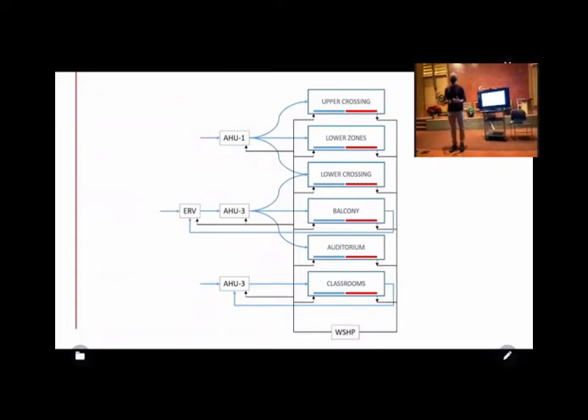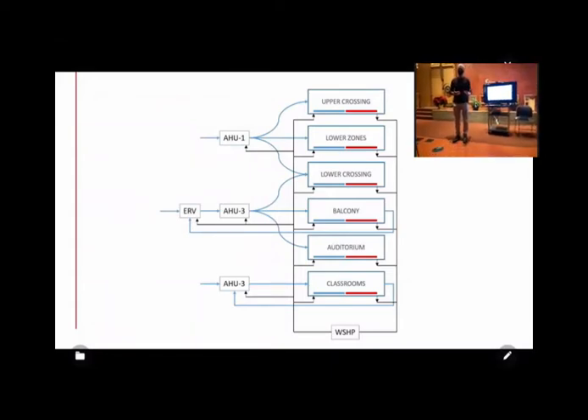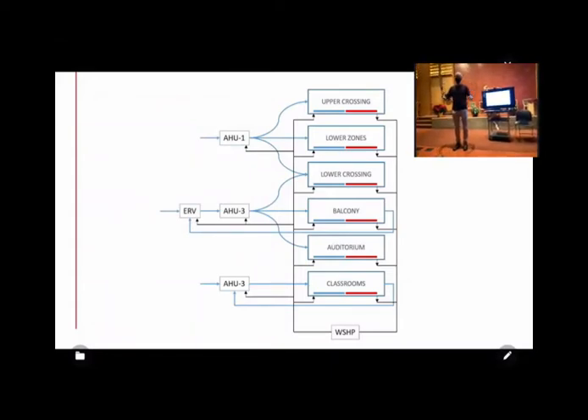It appears that with the Aldo Leopold building, once the natural ventilation cut out and you started cooling down, the floors took long enough to cool down that we could pretty easily dry out the air with the air handlers before there was a problem.